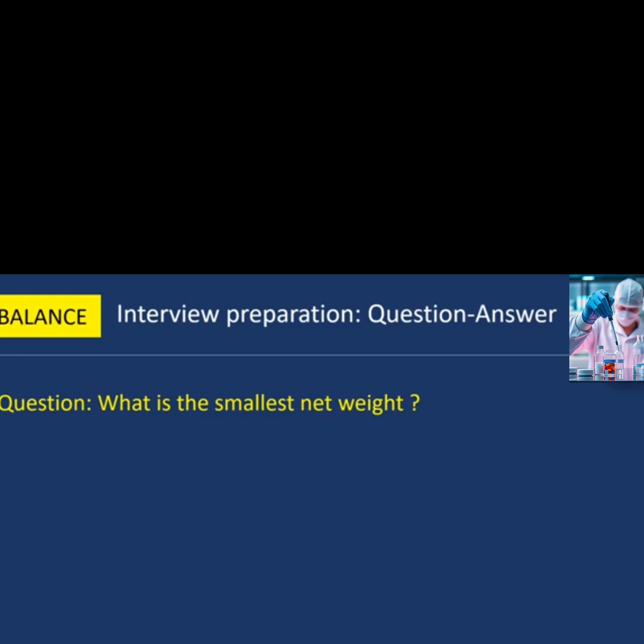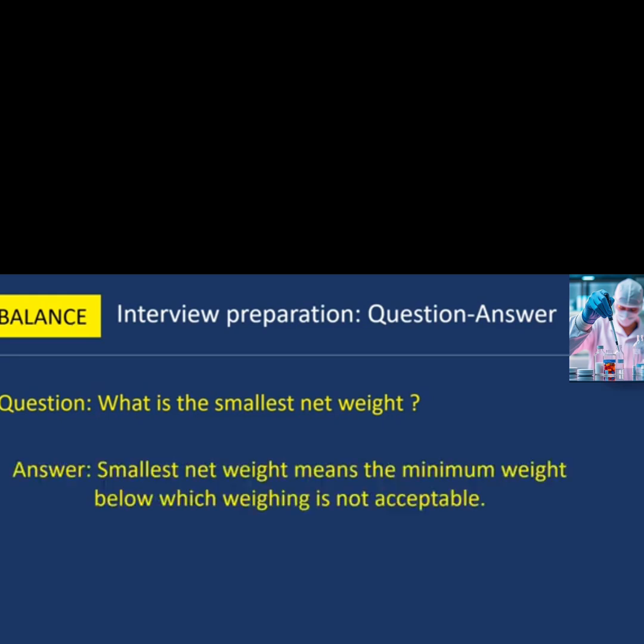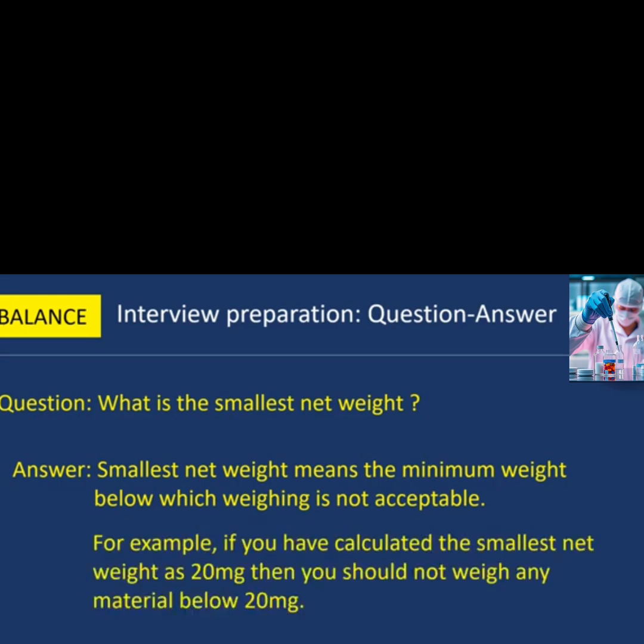Next question: what is the smallest net weight? Smallest net weight means the minimum weight below which weighing is not acceptable. For example, if you have calculated the smallest net weight as 20 mg, then you should not weigh any material below 20 mg.